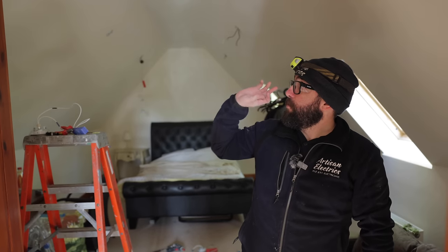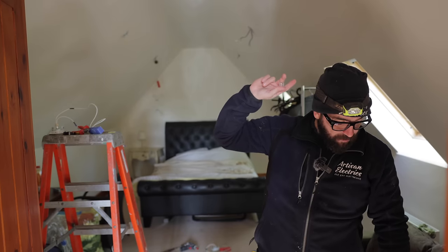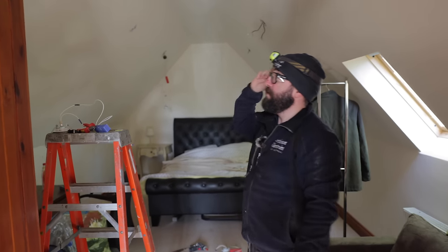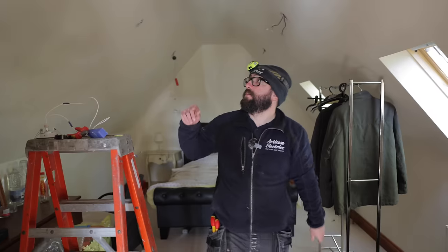So it appears that this piece of cable that goes from the switch to this light, to that light, I'm getting about 3.6 megohms. But when the next cable is connected, that jumps back down to about 1.5 megohms. But when I test that cable going away on its own, I'm getting about 3 or so megohms as well.